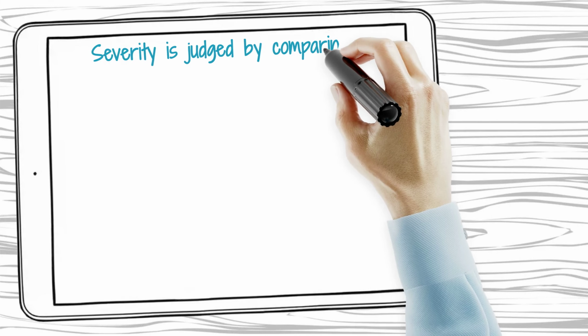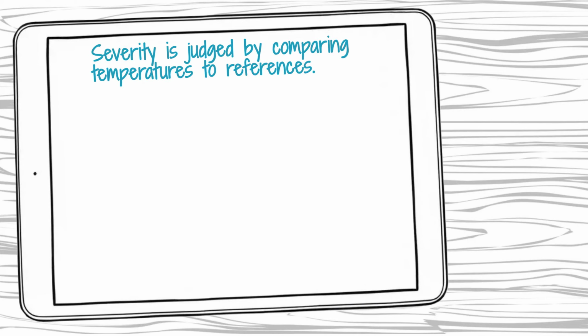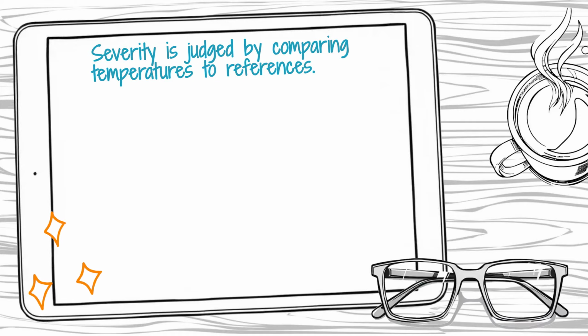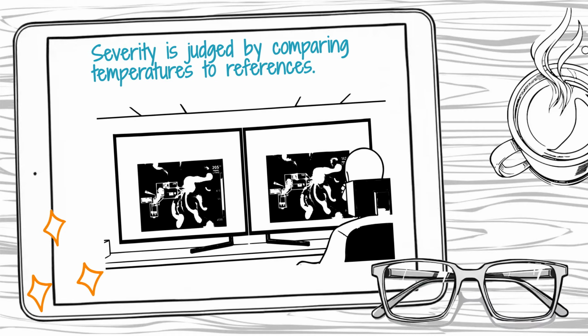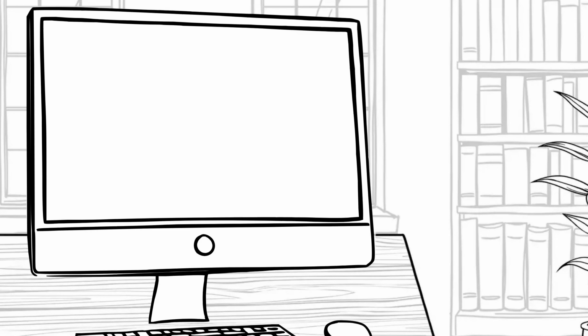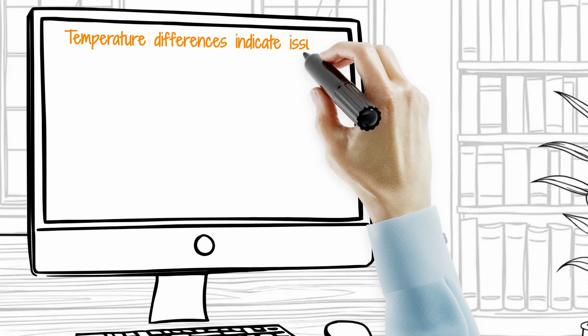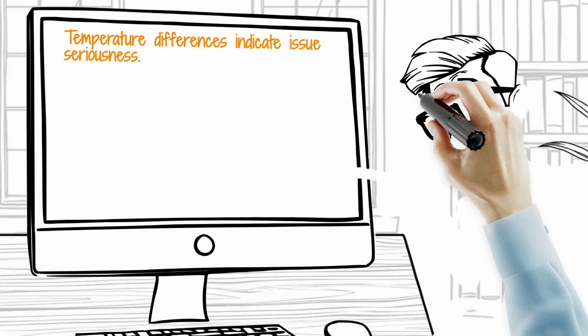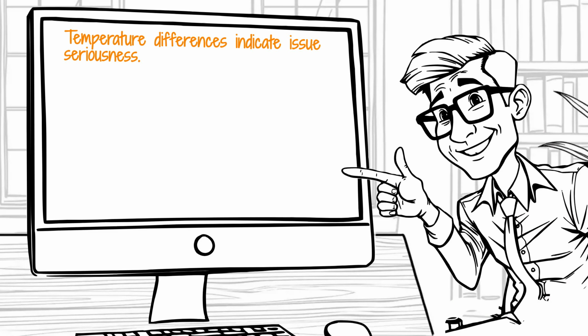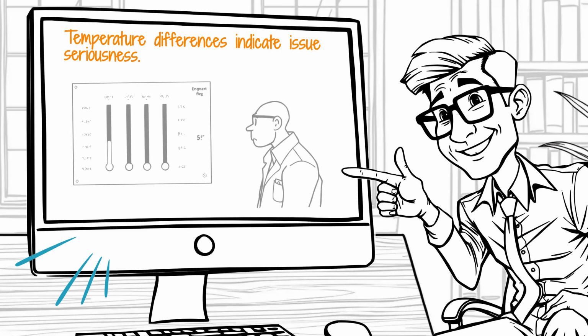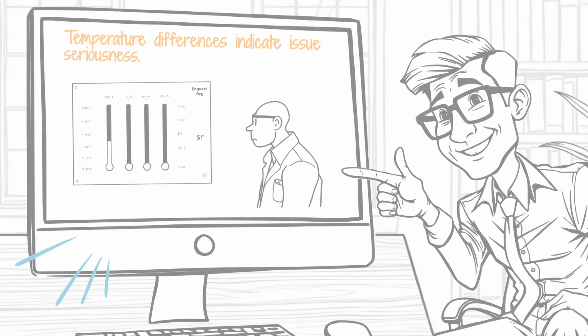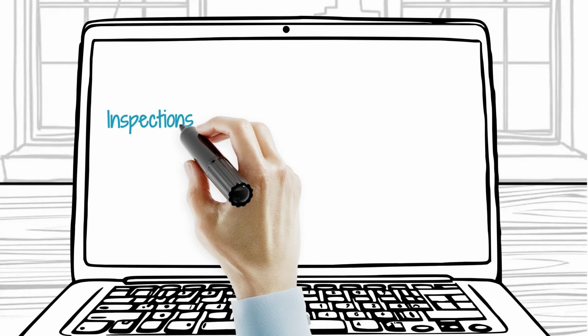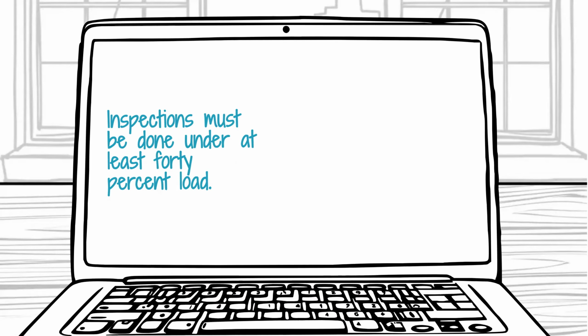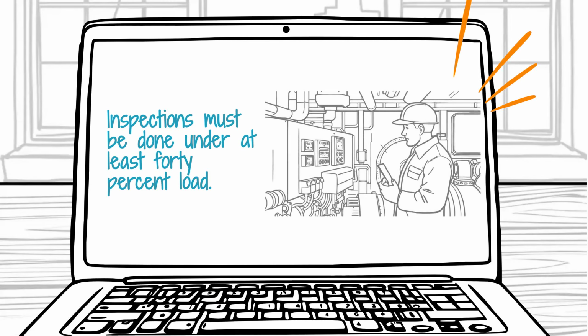Interpreting the severity of a fault is typically done using temperature delta criteria, which compares the temperature of the suspect component to a similar loaded reference component or the ambient air. A temperature difference of a few degrees might suggest a minor issue requiring monitoring, while a difference of over 15 degrees Celsius usually indicates a serious deficiency that needs immediate intervention. It is also vital to perform these inspections while the electrical system is under at least 40% load, because a fault may not generate detectable heat if the current flow is too low.